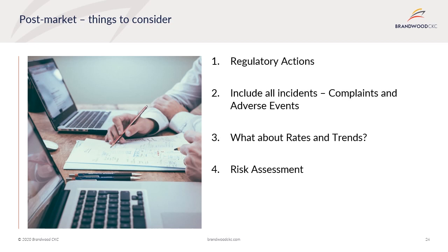So what are some things that you should consider when looking at your post-market data? Firstly, your regulatory actions. Any regulatory actions that have been taken on the subject device should be discussed in detail. This includes recalls and corrective actions. It's really important to not avoid discussing something. Secondly, include all the incidents.